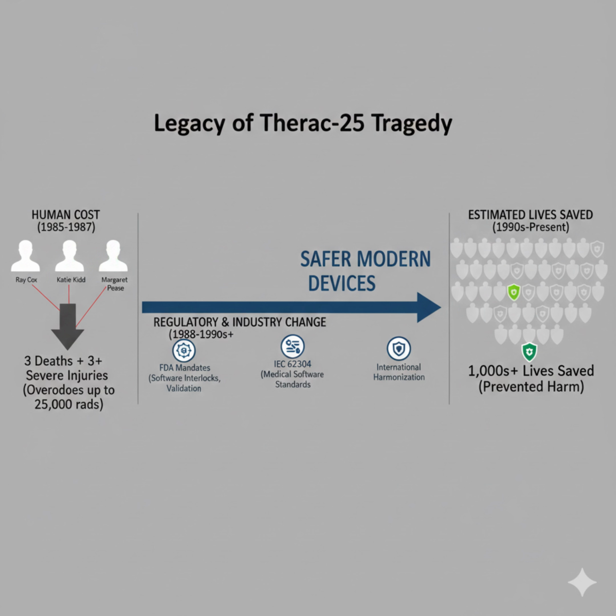Technical and design changes. Modern linear accelerators incorporate multiple layers of protection. Hardware interlocks, physical switches, and sensors verify that beam-shaping components are correctly positioned before the beam can fire. These operate independently of the control software. Redundant monitoring. Multiple independent dosimeters measure the delivered radiation. If readings don't match expected values, the beam automatically shuts off.